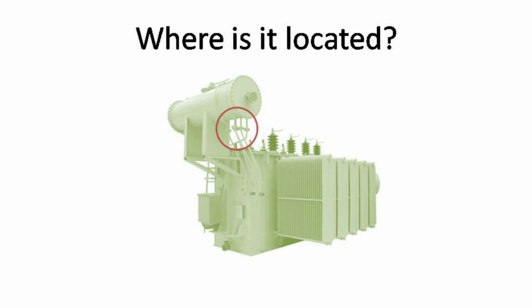So, keeping this idea in mind, the Buchholz relay is actually installed on the piping between the main tank and the conservator tank to detect these gases being produced. So the Buchholz relay would actually be installed in the place I've circled in front of you right now.